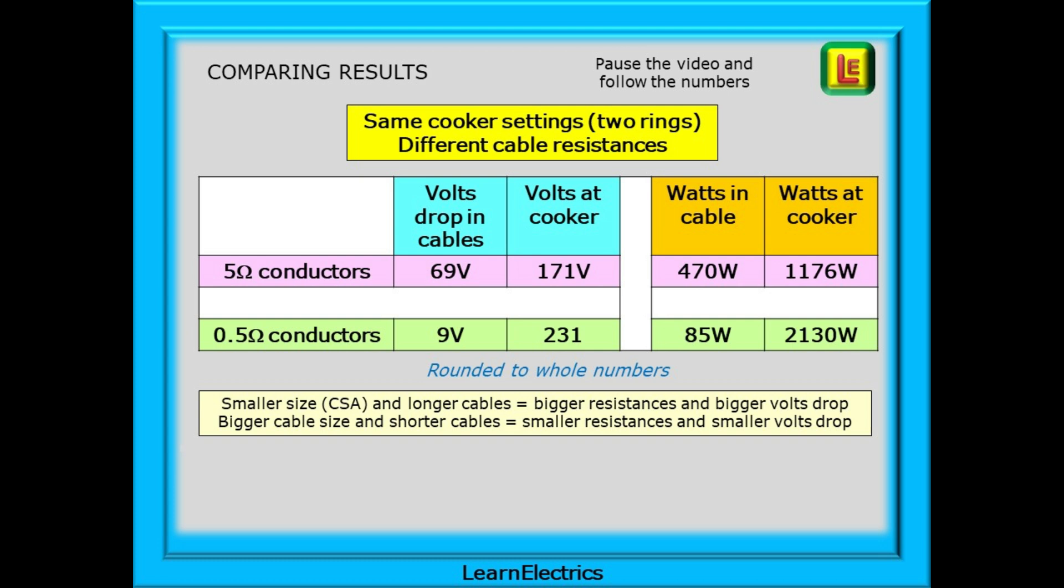Pause the video and look at the differences. This is the same cooker settings with two rings turned on, just different cable resistances. Before we had 35 volts lost in the cable. Now it is less than 5 volts. Before we had just 170 volts at the cooker. Now the cooker has 230 volts available and the power has jumped to a massive 2130 watts at the cooker. Almost all the power in the circuit is at the cooker rings, the elements, just where it should be. This is a much more efficient use of the power available. Lower cable resistances make for smaller voltage drops and more efficient circuits.